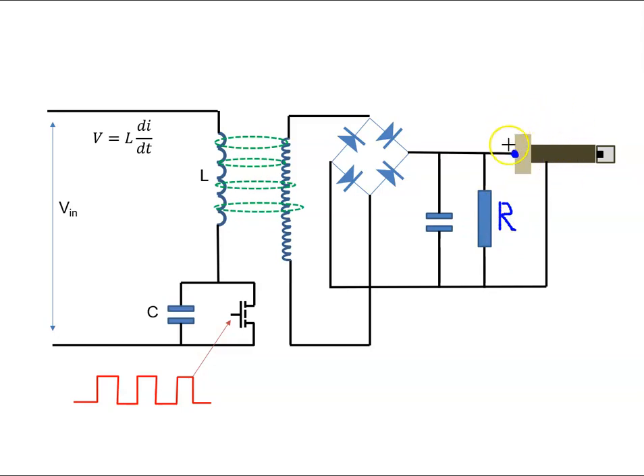If you're going to work with igniter plugs, you wait for an amount of time before you start working with them, because that is to allow the capacitor to discharge through this resistor. That could be anywhere between five and ten minutes. I think the recommended time is ten minutes.